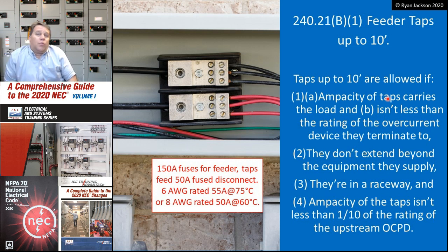And then out of that 30 amp fuse disconnect, I added the receptacle. Now, that was more work than I wanted to do, but compared to getting to the other side of the house and having to pull a 10 gauge home run all the way back across the house, it was a lot easier. And really, the hardest thing about this for me was simply remembering that that was an option. Once I remembered the tap rules, I was in the clear. It was easy as could be.